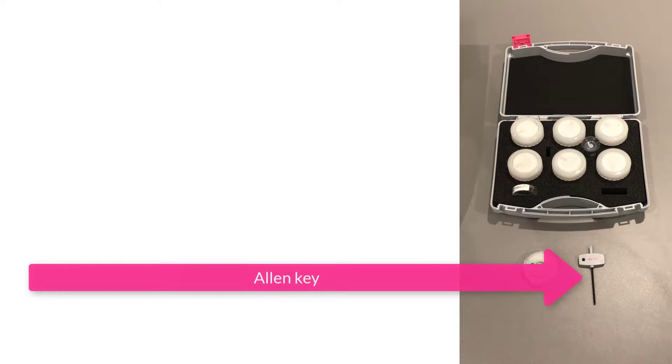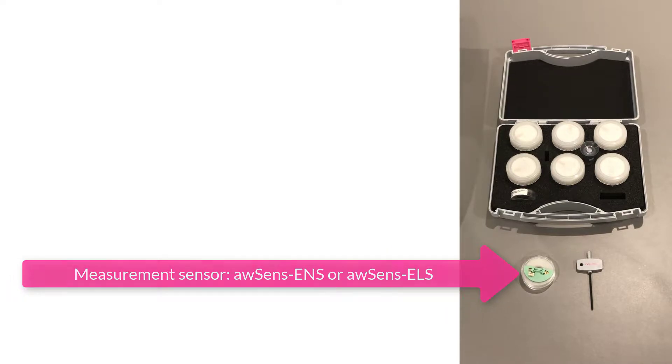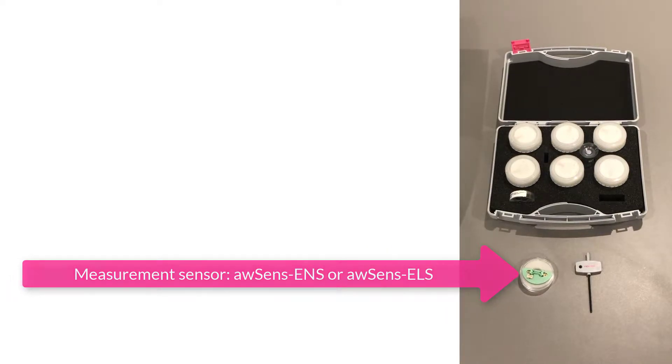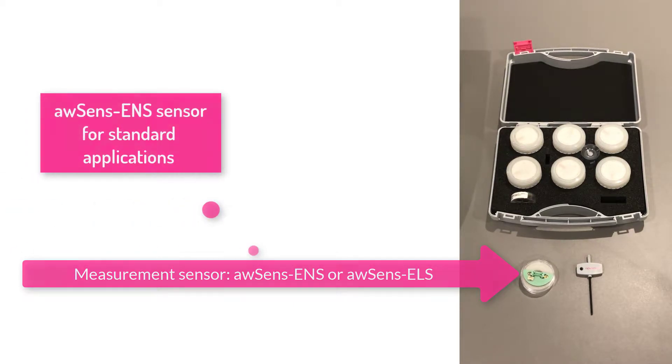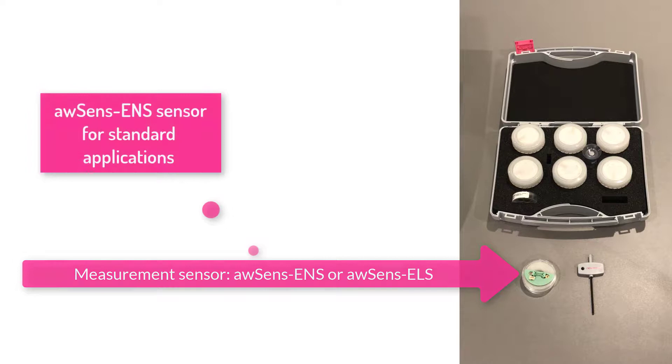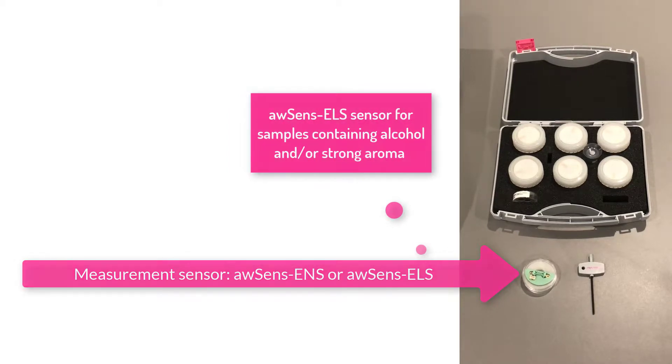An Allen key, which was included in the kit and can be found in the SALT standard case. A measurement sensor as a spare. Please consider that there are different versions available: the awSens ENS sensor for standard applications, or the awSens ELS sensor for samples containing alcohol and/or strong aroma.